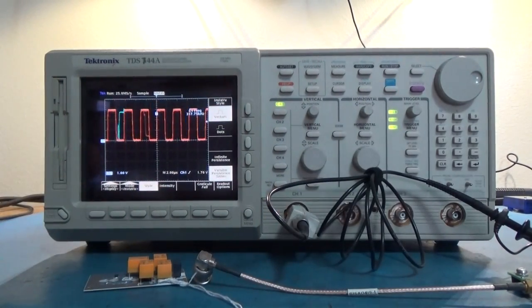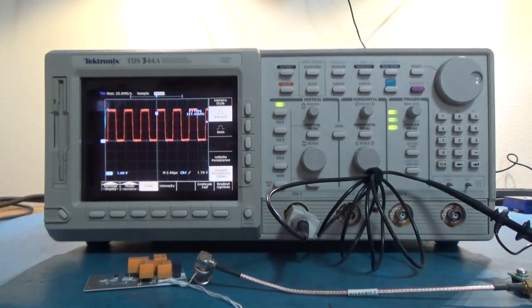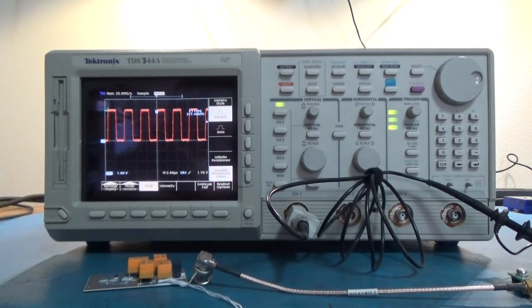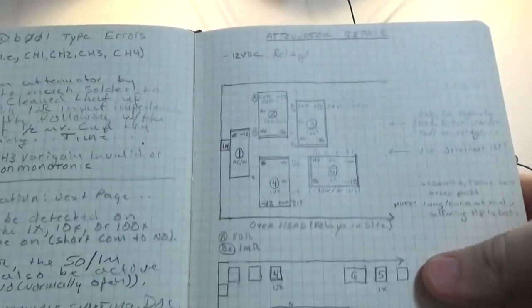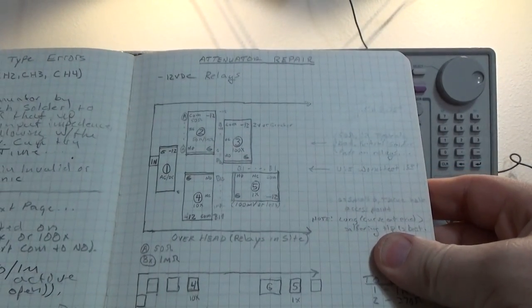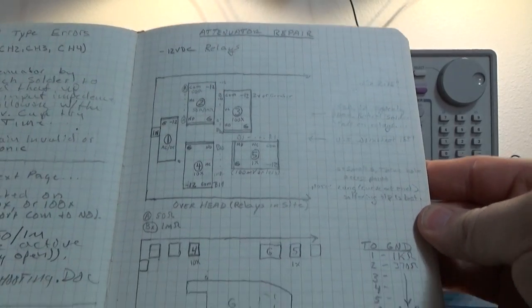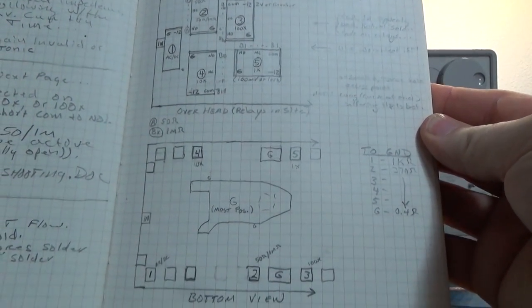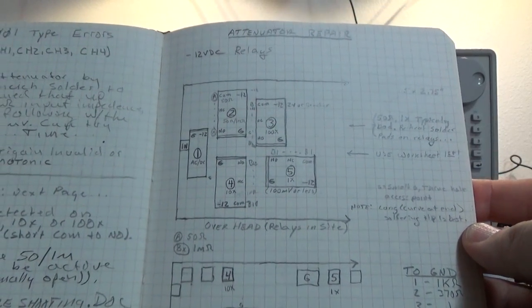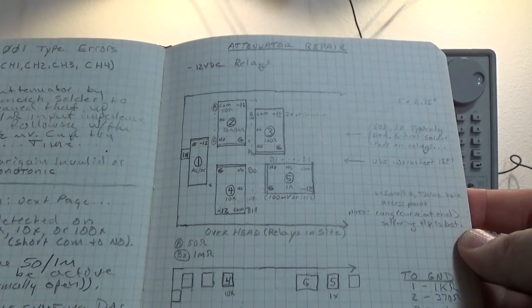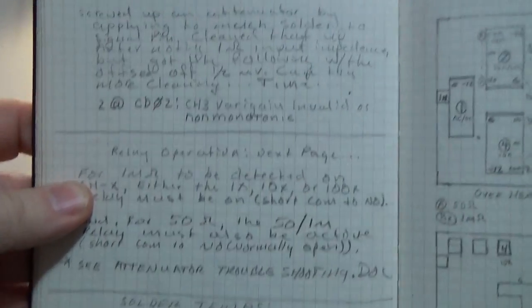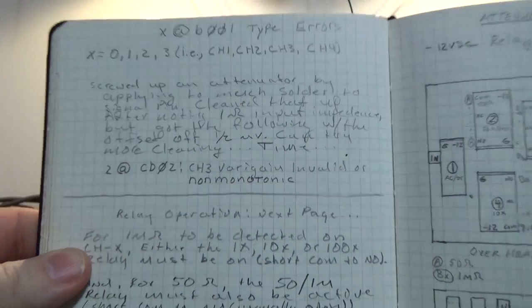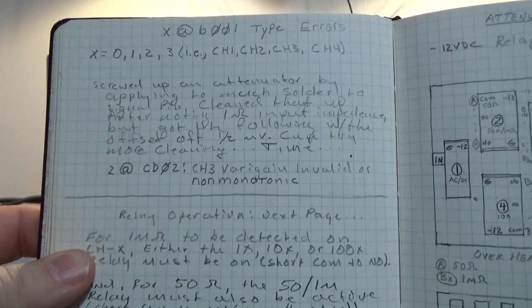I have a print here somewhere that gives me some ideas on the attenuators. I've done a little research over the years. So there's your attenuator. This is your cheat sheet that tells you how to kind of troubleshoot and zero in on stuff. If you want to know which is your 50 ohm, 1 megohm attenuator thing, relay for it rather.